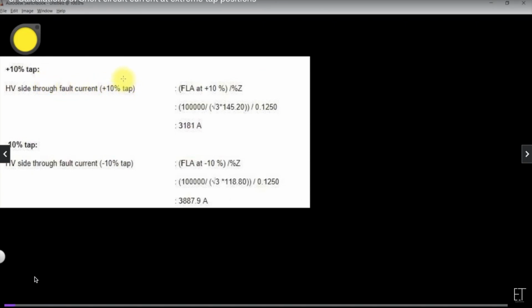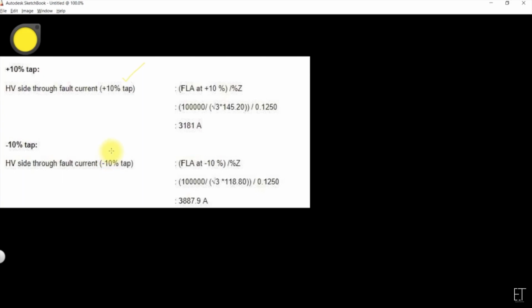Welcome back. In this section, we will calculate the high voltage side through fault current at plus 10% tap position and minus 10% tap position. In the last session, we learned how to calculate the fault currents at the HV side and at the LV side. One option is to find the short circuit MVA by dividing the MVA of the transformer by the percentage impedance. Then using the formula under root 3 V into I, you can calculate the short circuit current at the HV and LV sides. This is one way of doing the calculation.